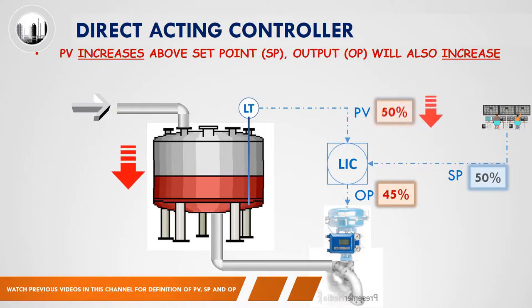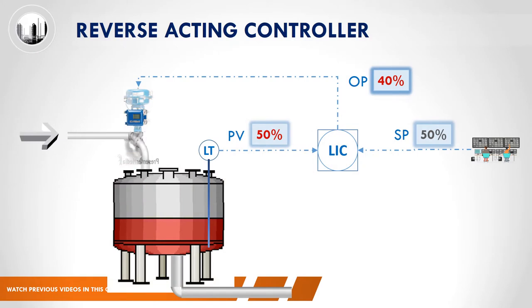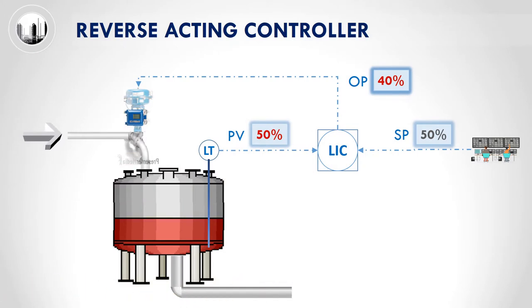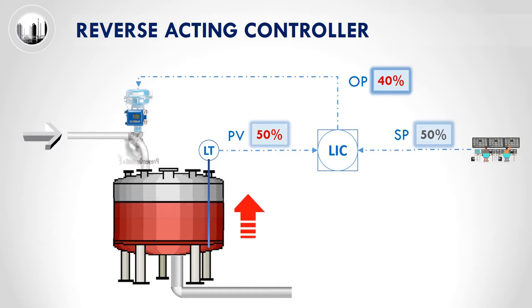Next, we will look at an example of a reverse acting controller. For this example, the setup of the tank is slightly different from the previous example. In this example, the control valve is located at the inlet of the tank. Again, we will evaluate the scenario when the level in the tank increases. The increase of the tank level will be measured by the level transmitter. When the tank level increases, the control valve at the inlet of the tank will close more to reduce the feed into the tank.